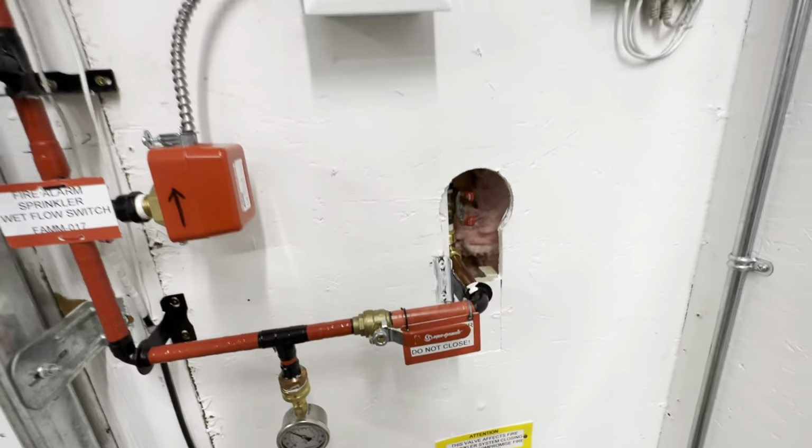Okay, this is just supposed to be a short video just showing the fire alarm going off, because I'm sure I'll put in some camera clips of it, because I do that whenever the fire alarms go off falsely. This false alarm was caused by the sprinkler flow switch tripping.